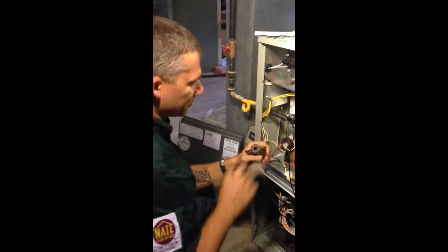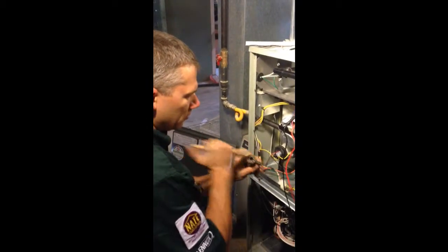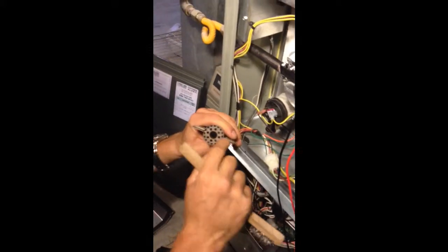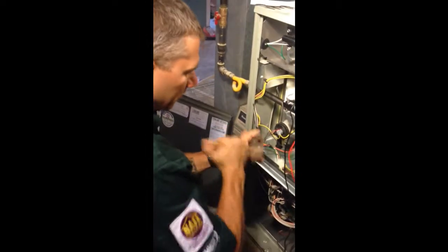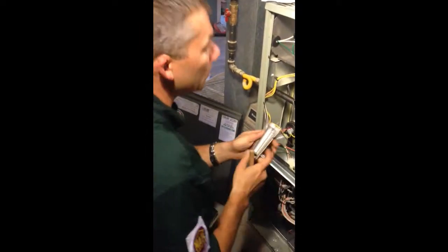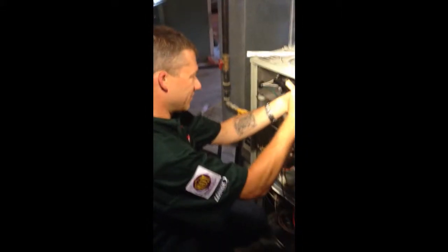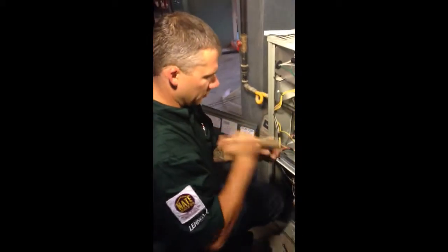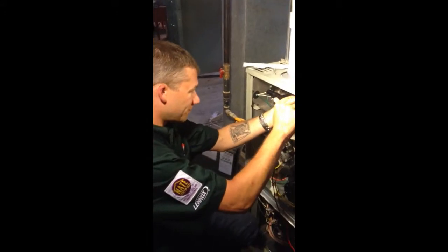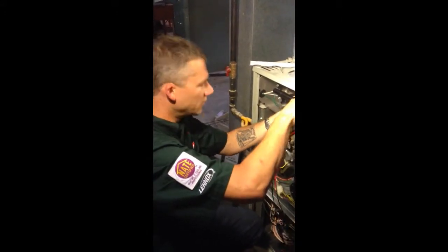The big important part is to pull these out, and you want to clean these little bridges, because the gas comes out here, and the gas jumps from one burner to the next. So you want to make sure that there's not a lot of corrosion built up. So you pull them out, and what I do, and I'm not even positive whether this is good or bad, it's like rotating tires. I'll take them out, but I'll rotate them all over one. It's kind of like rotating the tires on it. That way, hopefully they corrode evenly. Evenly, yeah.